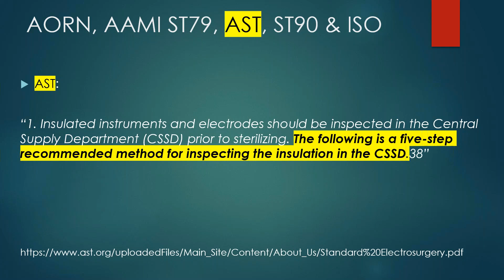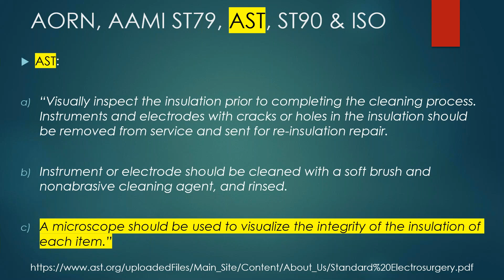Again, AST goes on to say the following is a 5-step recommended method for inspecting the insulation in the CSSD. There are a few points here, but the one I focused on was that a microscope should be used to visualize the integrity of the insulation of each item. I do want to point out that yes, we're talking about insulated devices and testing with that tester, but we also want to make sure that you have the right magnification and lighting, and in this case they're actually saying a microscope, to be able to see other damage. Because what we do see is damage, but not to the point where there's a complete breakthrough into the exposed metal. That is still damage, even if the leak tester you're using says it's passing. Any type of damage can harbor bacteria or lead to bad patient outcomes.